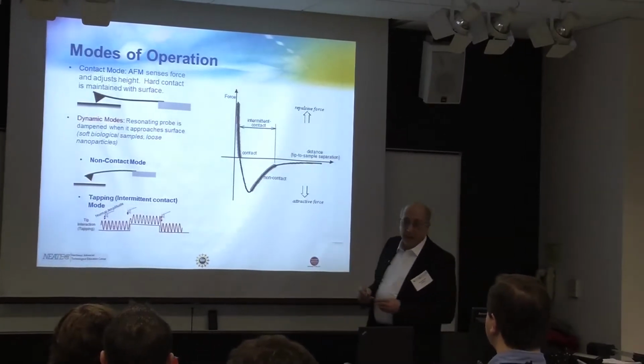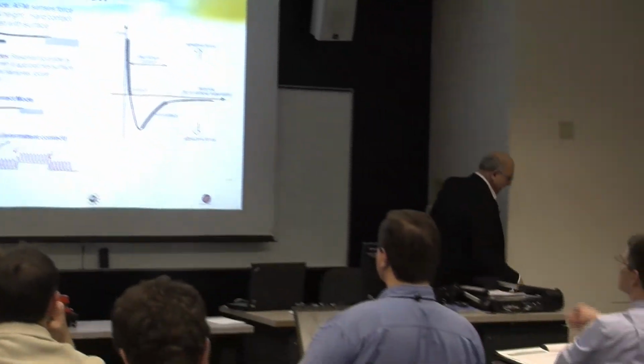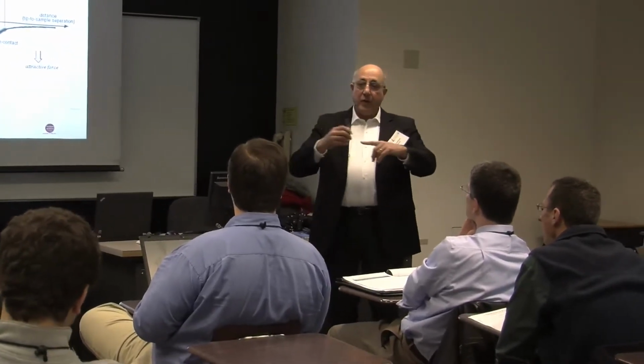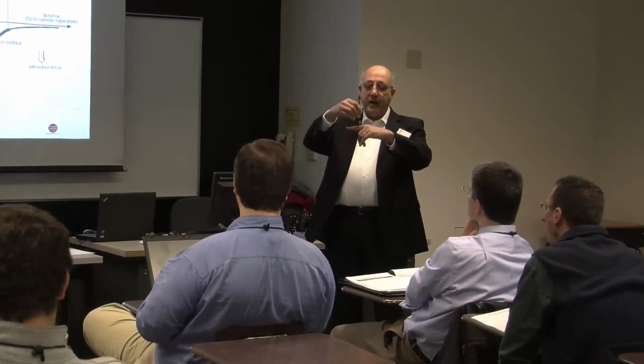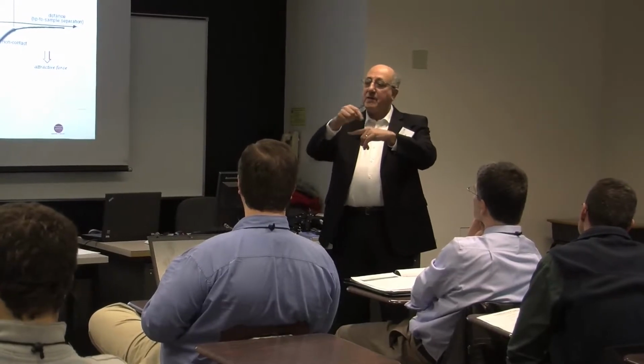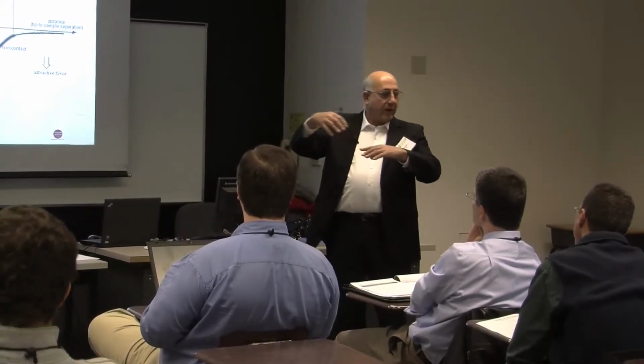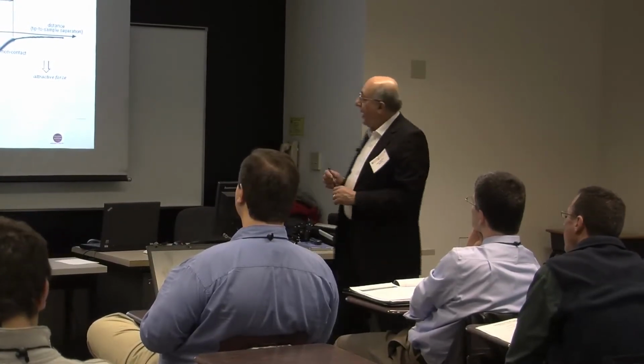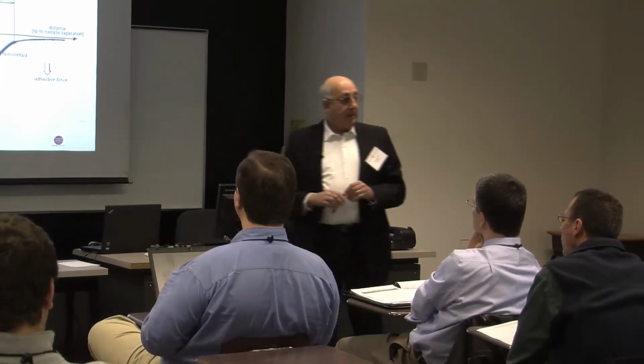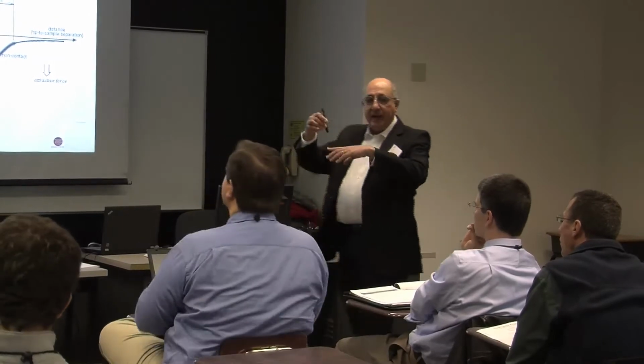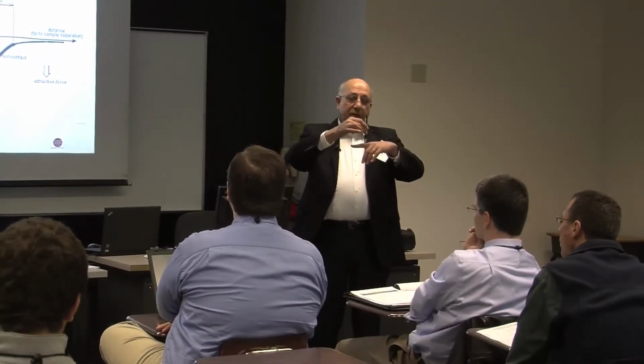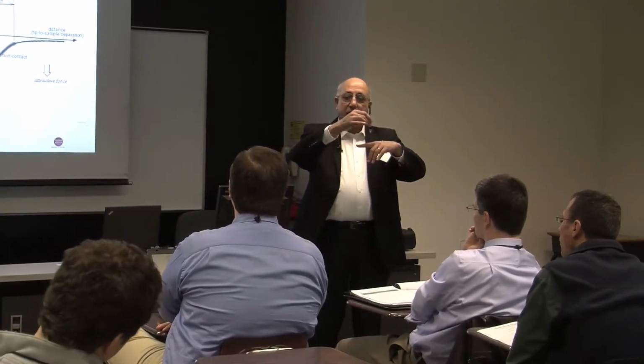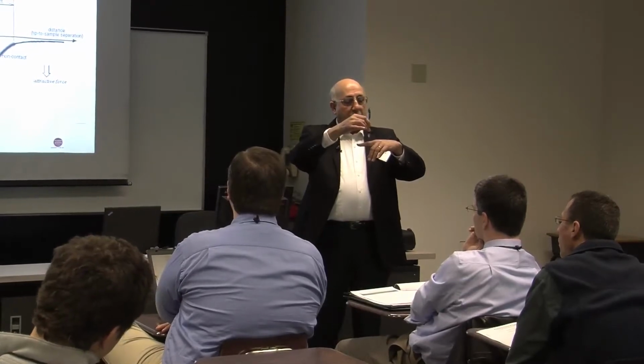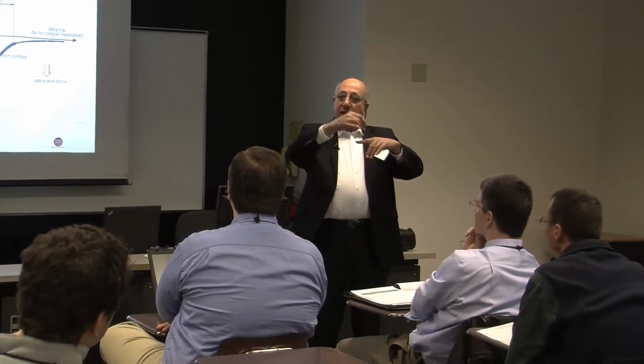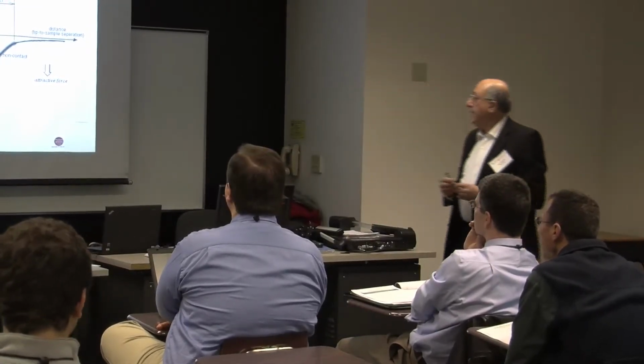The other way we call dynamic mode, where the tip is not in contact with the sample. One mode of the non-contact is to have the tip moving at the same distance from the sample all the time, so it will follow the contour of the sample, but it will never touch it, okay? Another way, probably better, is what we call tapping, okay? You can have the tip just touching the sample once in a while. Just touch the sample and then move the tip on, and then move a little bit, touch again, and it does this all the time.